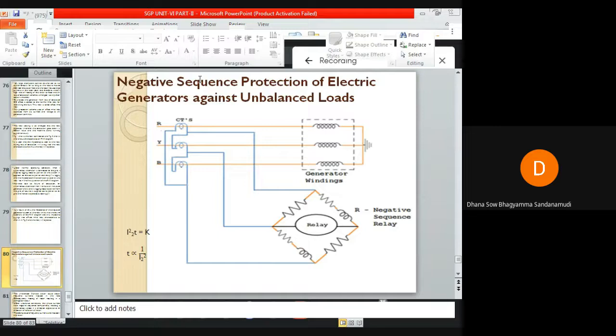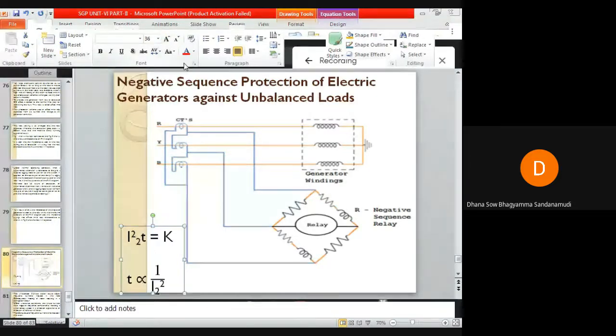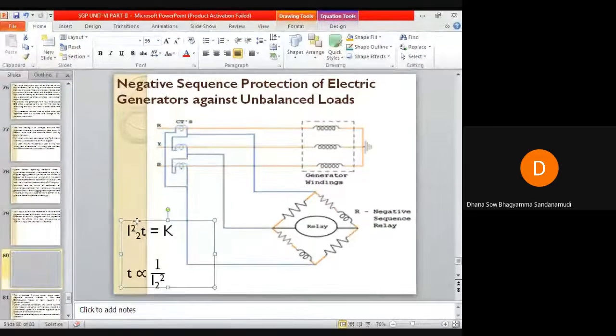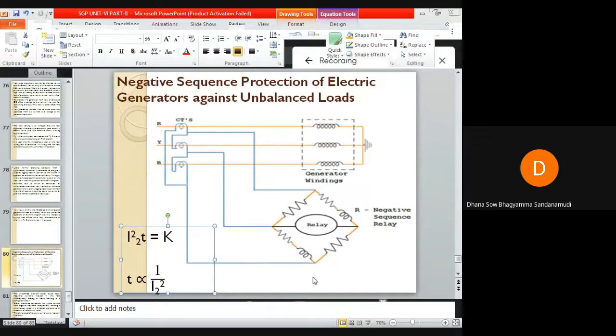The negative sequence heating will follow a normal resistance law and hence will be proportional to the square of the current. So the negative sequence relay operation will be proportional to the square of the current. The heating time of this machine will be largely a function of the cooling system employed. How much time is taken for the rotor to heat, due to the unbalanced currents in the stator or the unbalanced external fault which is not cleared quickly, will depend on the functioning of the cooling system. Usually it is expressed as I square T equal to some constant K, where T is inversely proportional to the square of the current.